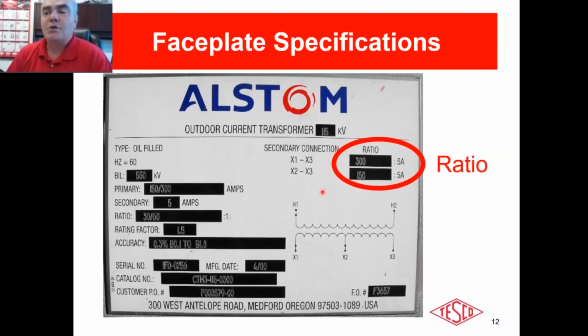The knock against the dual ratio is that, first of all, it didn't change anything in the accuracy, whereas the extended range actually not only improved the overall range that the transformer would operate at, but it also improved the lower end of that range dramatically, which we'll talk about in a few minutes. The bigger problem, though, with the dual ratios is that if you have one of these transformers out there, it's a perfectly good transformer. If we took it back into the shop and did a really good accuracy test on it, it would probably be approximately as good as the day it was manufactured. Very good transformer.